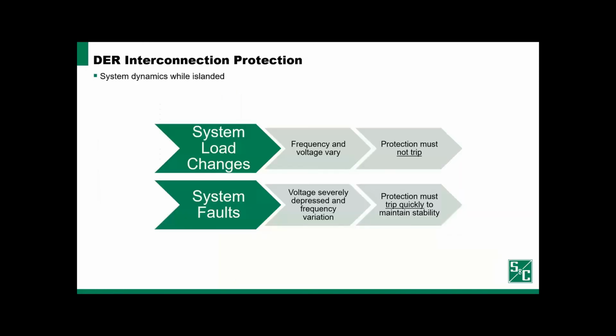System protection also needs to consider the system dynamics. And system dynamics can be significantly varying during microgrid islanded operation. When we have a small amount of generation online, when the system load changes, frequency and voltage can vary as a response. And this frequency and voltage variation in response to the load change should not cause the protection to trip. This would be undesirable and result in load being disconnected and customers outaged.